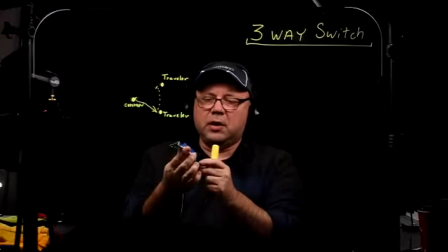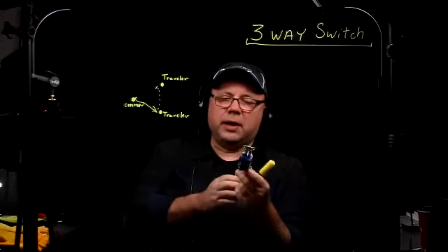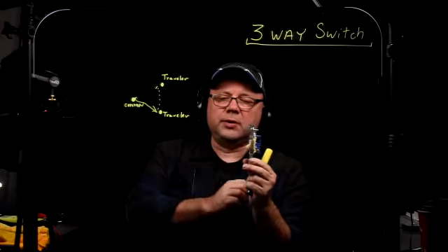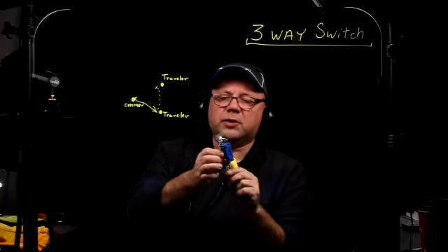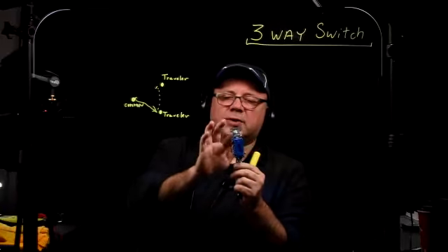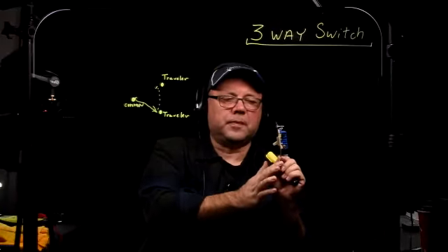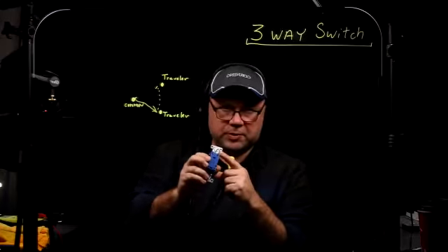Now, just hypothetically, if you have a switch with the terminals not labeled, obviously you're going to see which one is the ground or bonding terminal. Quite often the three-way switches, single-pole switches, or four-way switches will not have a ground terminal, because the ground or bonding is done by way of this chassis here, that is connected right to the box. But some of them do have a separate grounding terminal, depending on who makes it, who sells it, and so on.